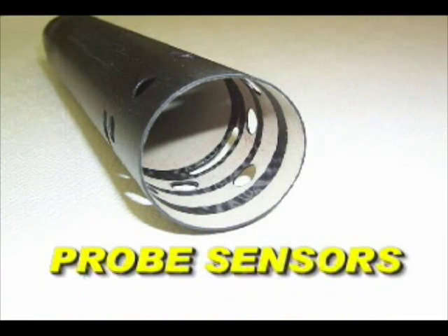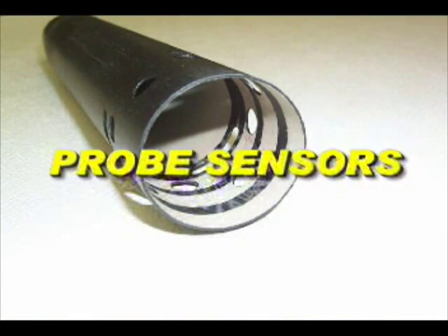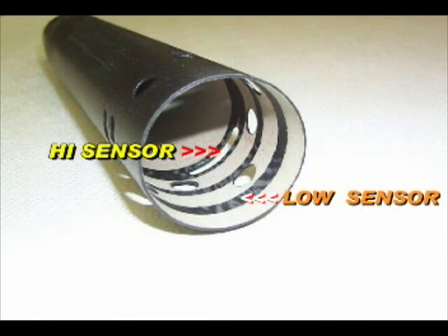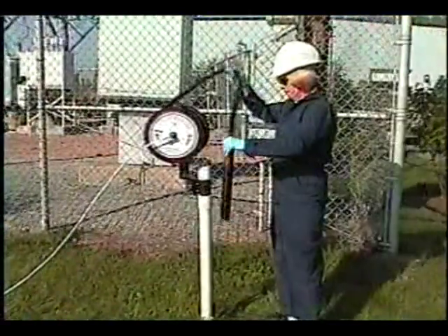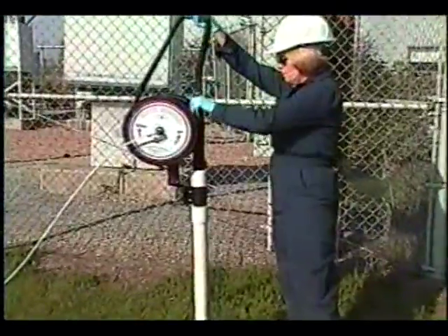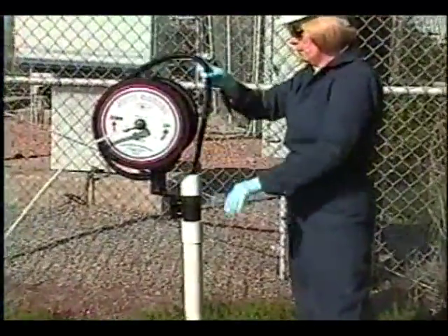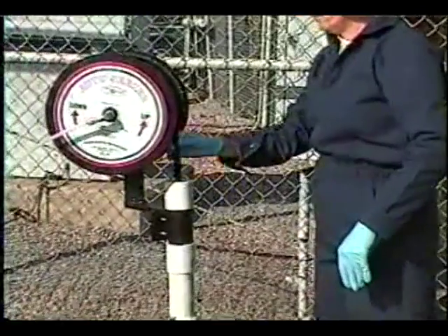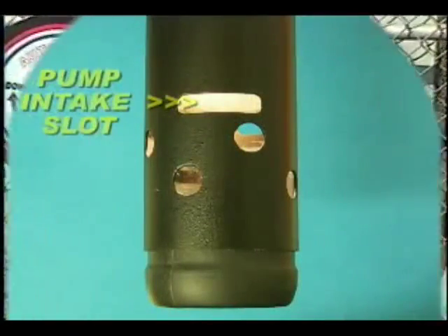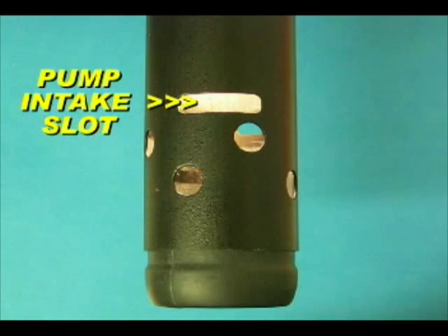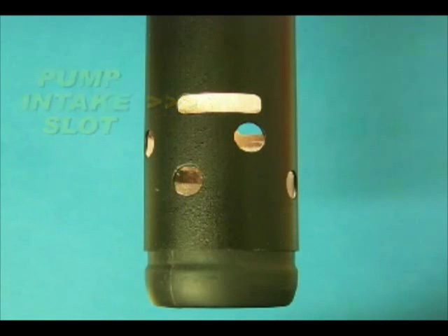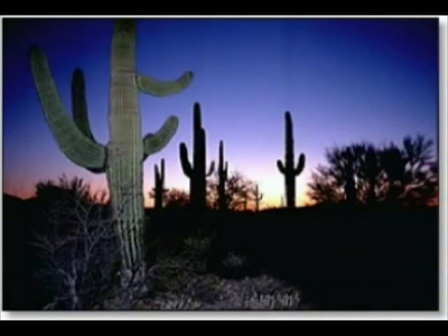The water product interface sensors are all solid-state carbon composite bands that are a spin-off of the spacecraft fuel gauging technology developed for NASA. The use of these interface sensors in the environmental industry is unique. Since they are all non-contact sensors, they are highly immune to biological fouling. The carbon materials used are very tough, will not corrode and deteriorate in the well. The pump intake slots are machined in the center of the sensing band and thus will instantly shut the product pump off when water touches it, preventing even the tiniest amount of water from being pumped.